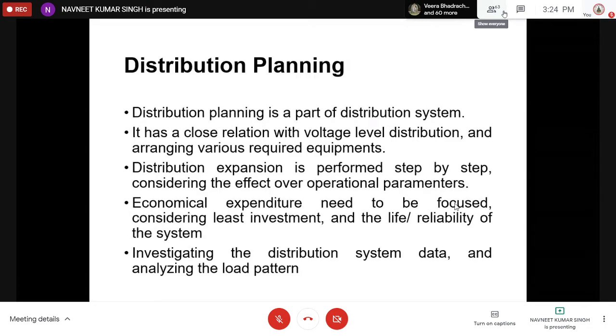Thereafter, distribution expansion is performed step by step; we cannot do it at a stretch. Why? Because as soon as we put one additional line, operational parameters like P, Q, V, delta—power factor angle, active and reactive power—change. So we need to take care of these as soon as we add an extra line, bringing parameters back to normal by adjusting the generating end, or if it drops too much, installing more generation, expanding step by step.